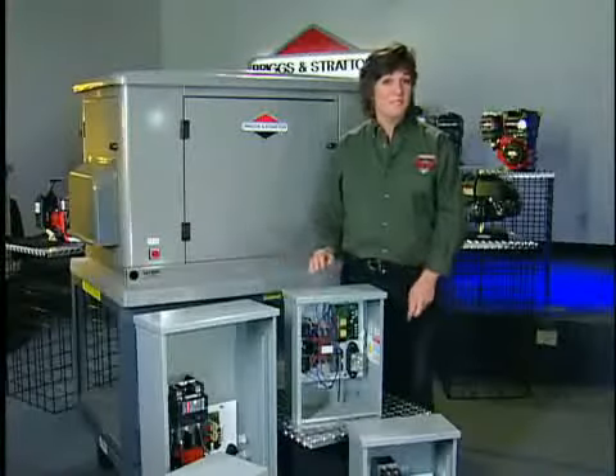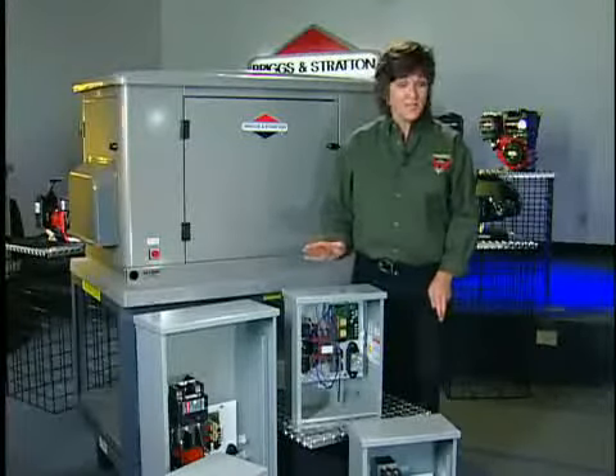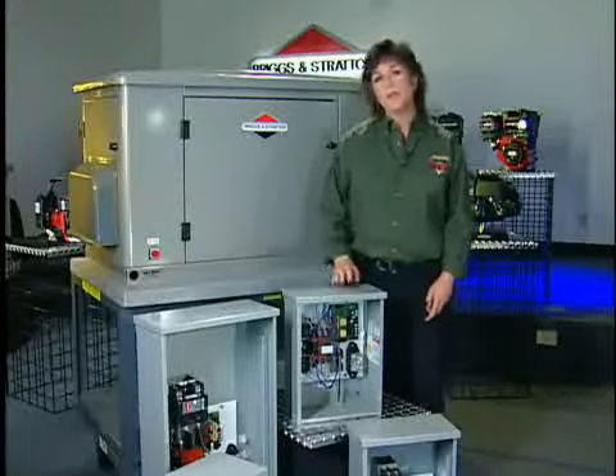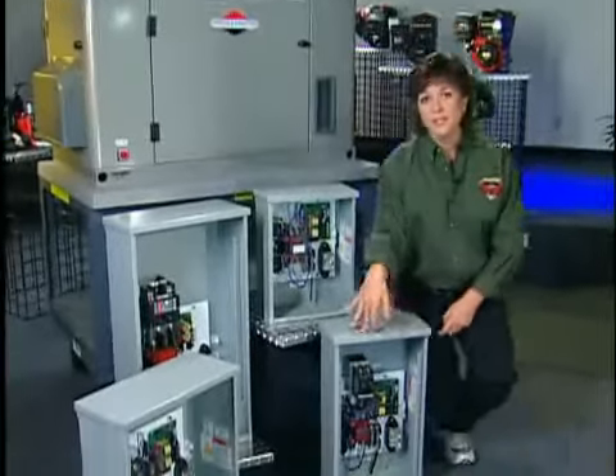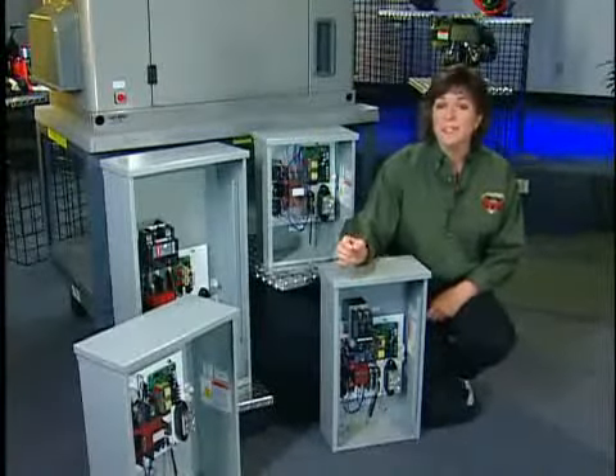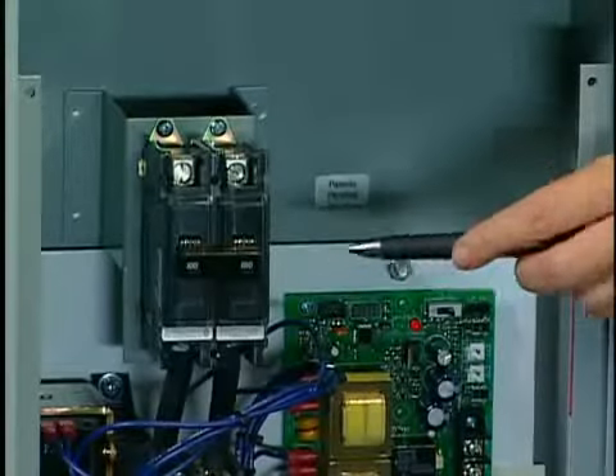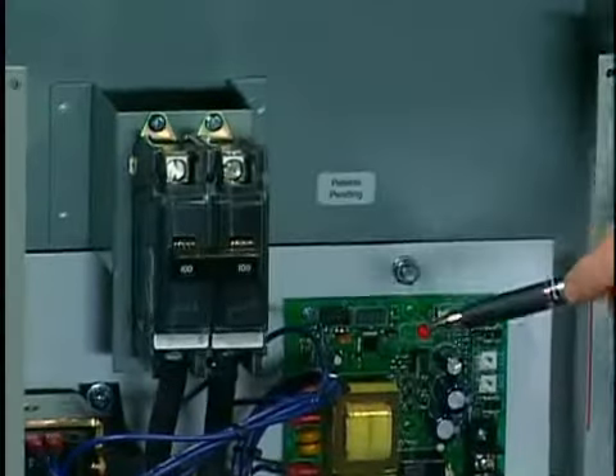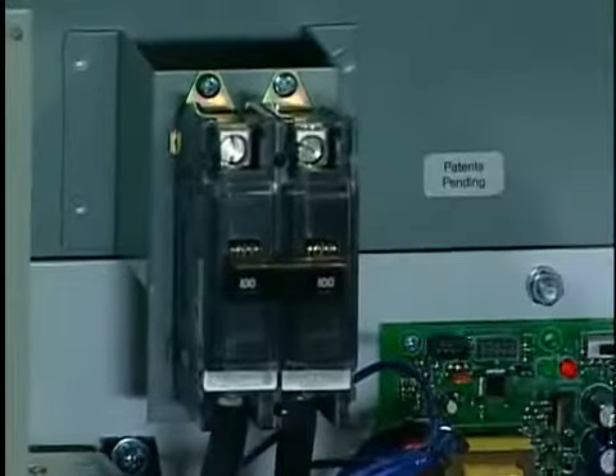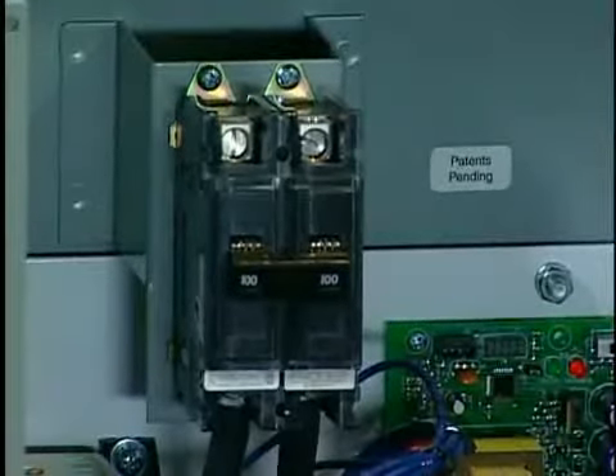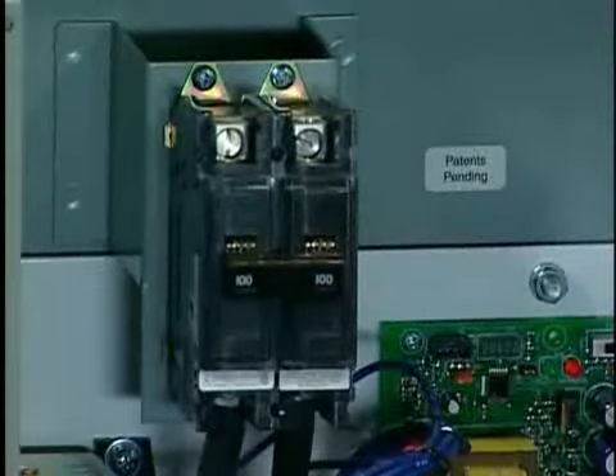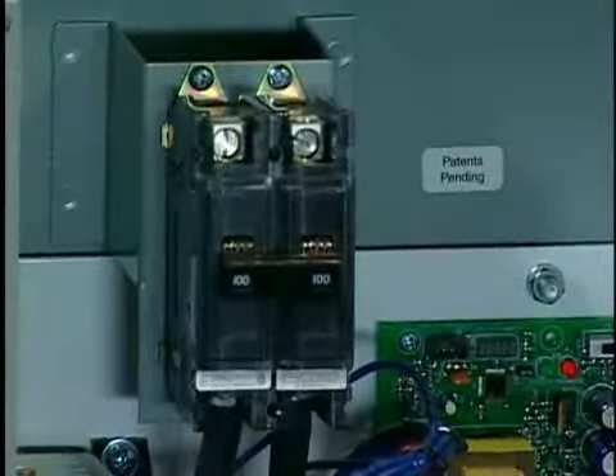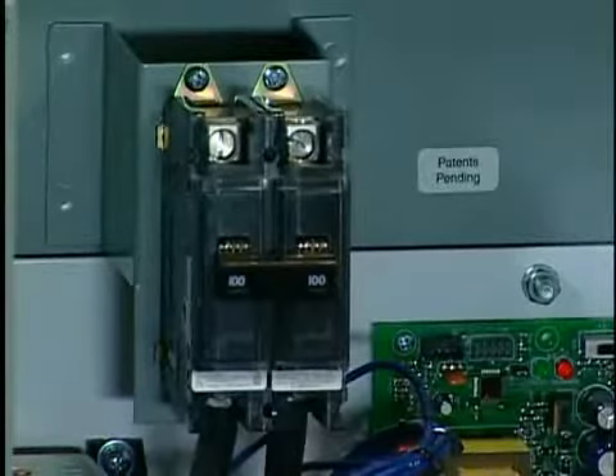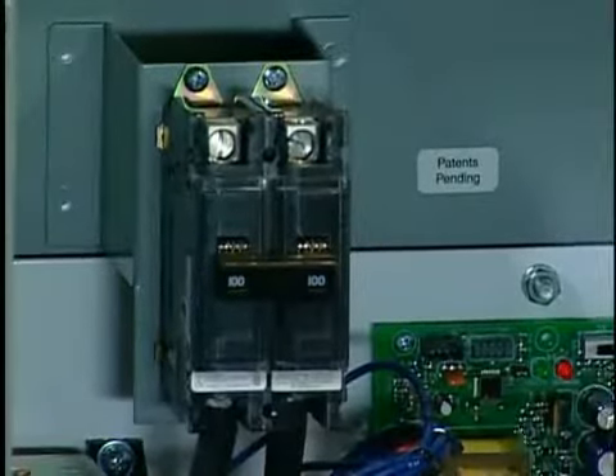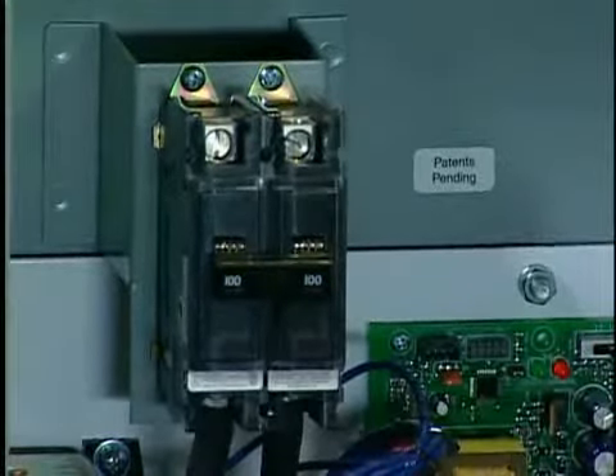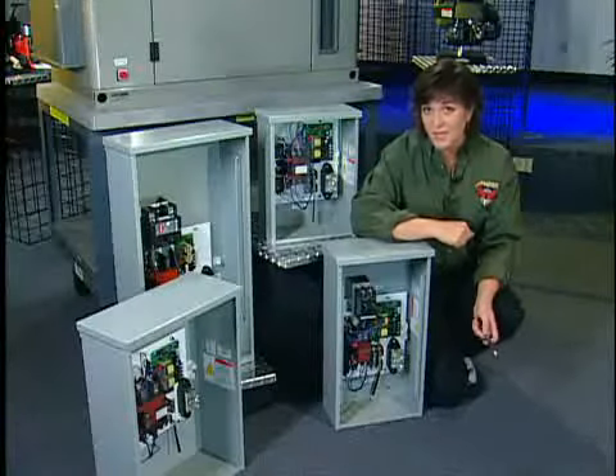Another part of our home standby generators that have seen a lot of changes are the transfer switches. There are three major changes that are taking place. The first one is a 100 and 200 amp automatic transfer switch with what is called a mainline disconnect. With this feature, the disconnect is incorporated in the transfer switch. For new construction, that means the contractor doesn't have to add an extra disconnect switch between utility power and the transfer switch. So that saves the customer money.